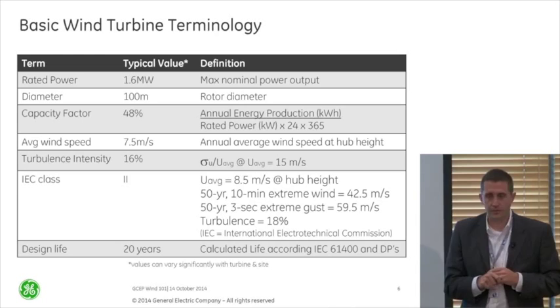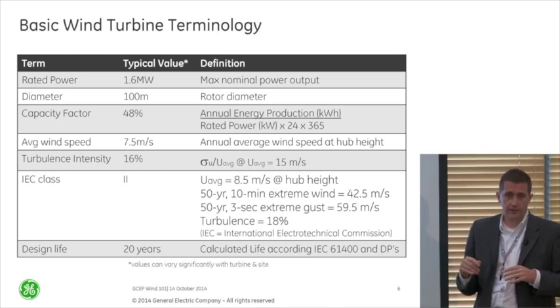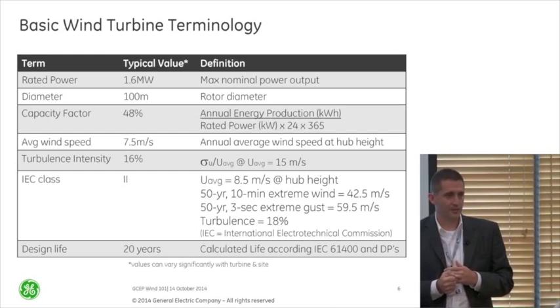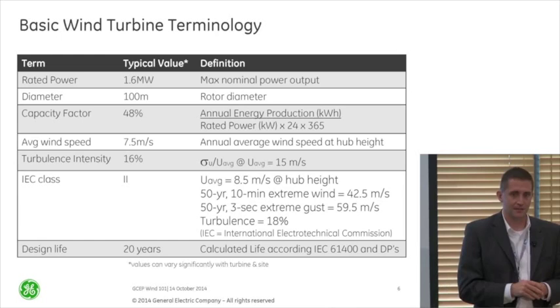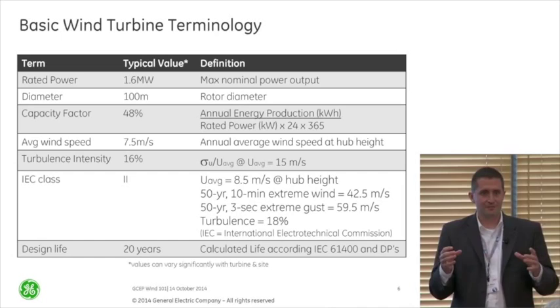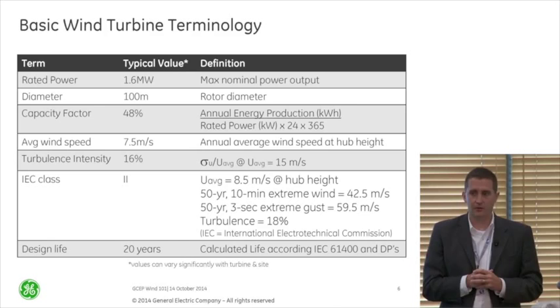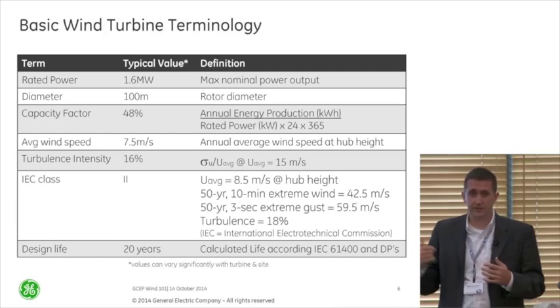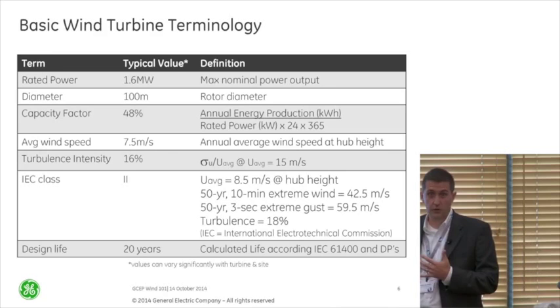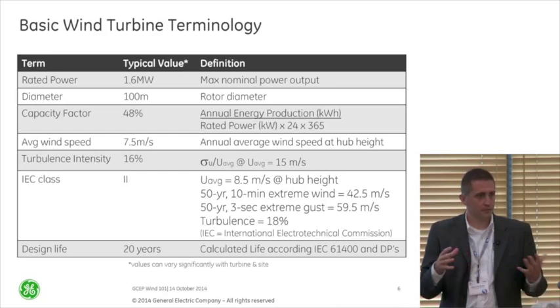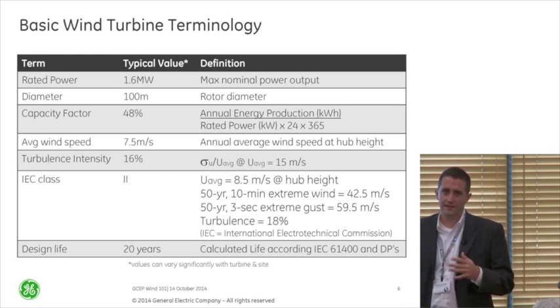When we talk about wind resource, we often look at the average wind speed of the site. Seven and a half meters per second is actually pretty good — you'd probably make a pretty good economic case in the US. Most of the stuff developed five or ten years ago is closer to eight and a half meters per second. In Germany, where they have lower wind speeds, they'll do it at six and a half meters per second. If you drop below six, it's really difficult to make the economics work, and in the US if you drop below seven it's still pretty difficult.